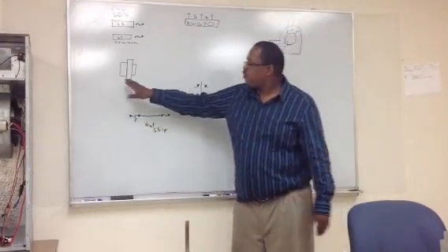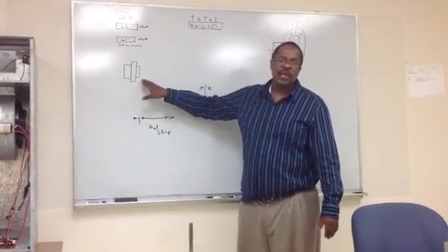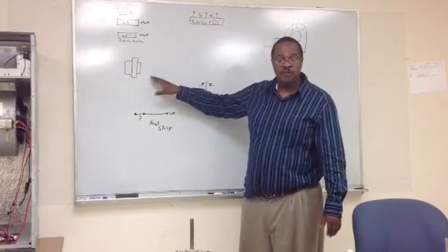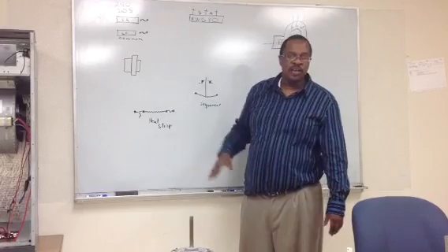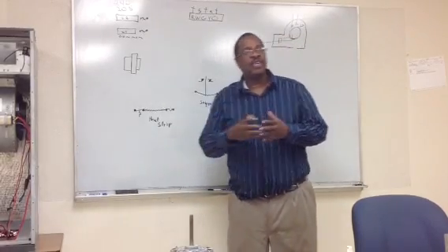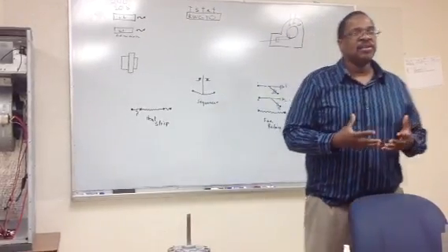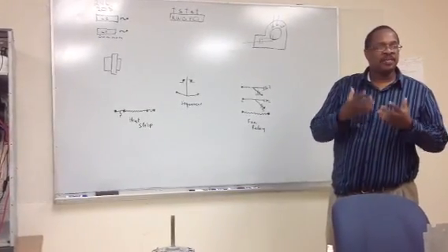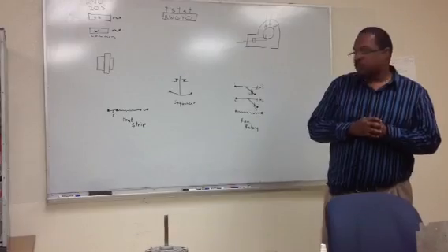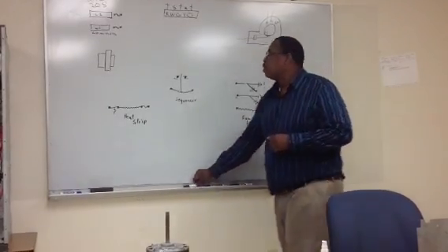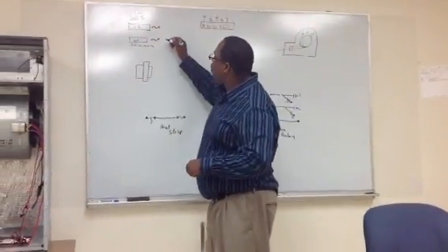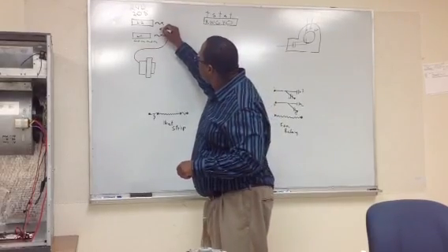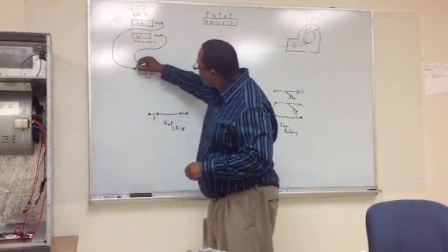But the transformer is what reduces that power. It takes the main power and reduces it or steps it down to 24 volts. Now we know in electricity, as long as it is within 10%, it's good voltage, we can use it. But if it's below 10%, plus or minus 10%, then we can run into some problems. So let's then get power over here to our transformer.